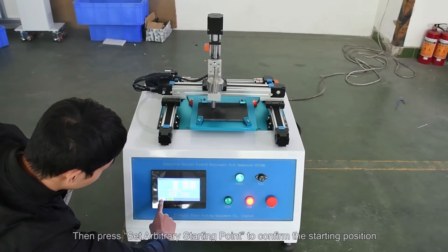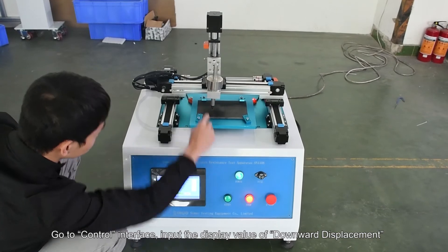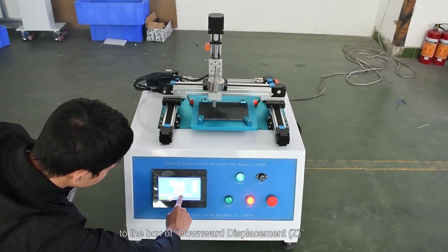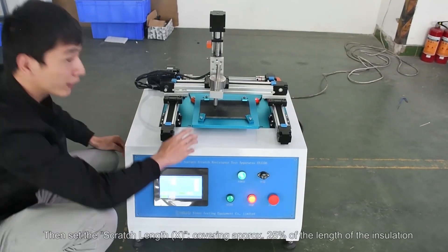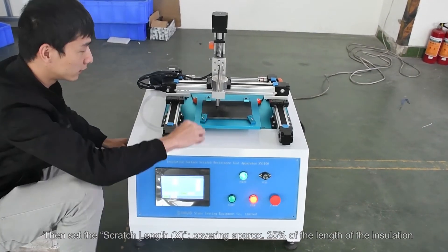Go to control interface. Input the display value of downward displacement to the box of downward displacement Z. Then set the scratch length X covering approximately 25% of the length of the insulation.